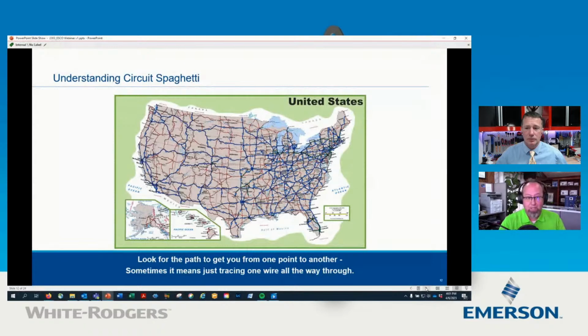I had a printing company client with HVAC equipment to cool their press rooms. Occasionally the owner would say something wasn't working right in the cooling system inside the German-made press, which had a schematic—but everything was in German. So you'd sit down and trace one wire at a time until you found the relay that wasn't closing and replace it. He was thrilled because I saved him the cost of a technician coming from Germany to fix one relay. But it's one wire at a time, and that can take time.